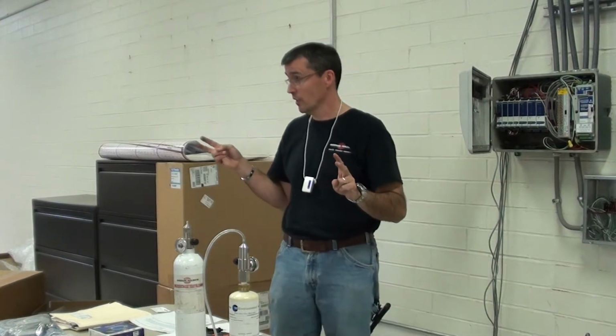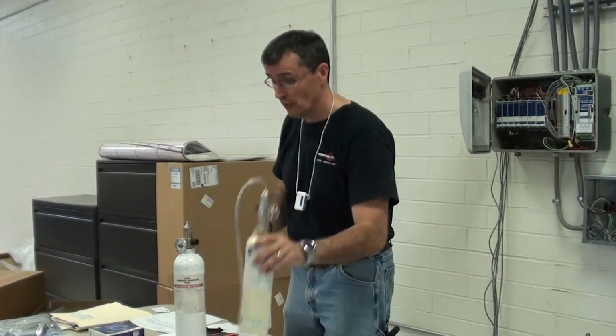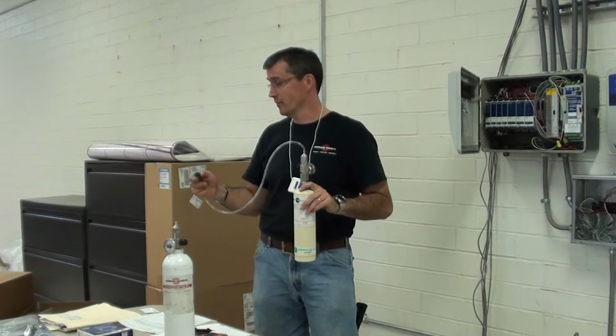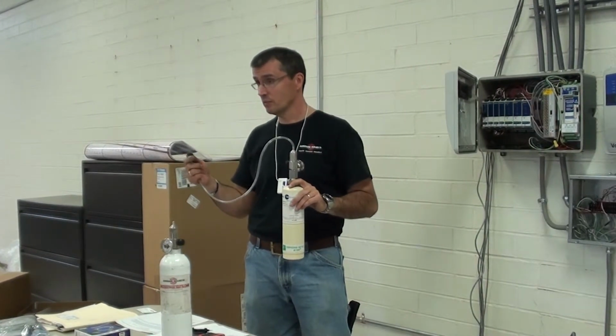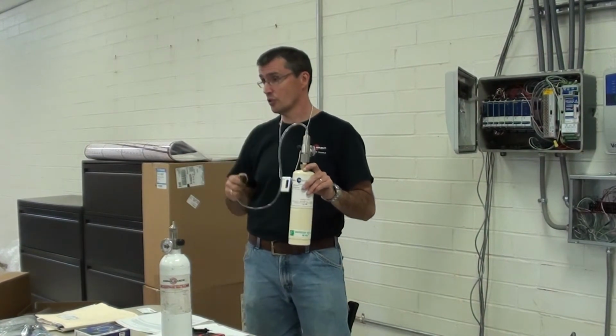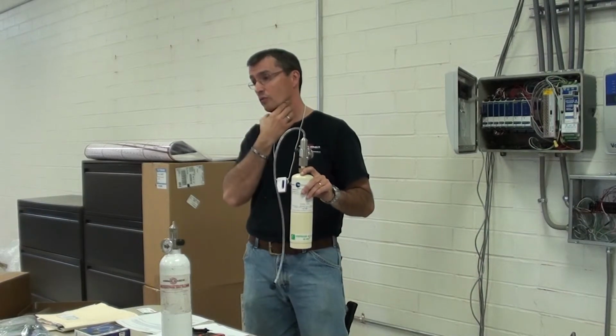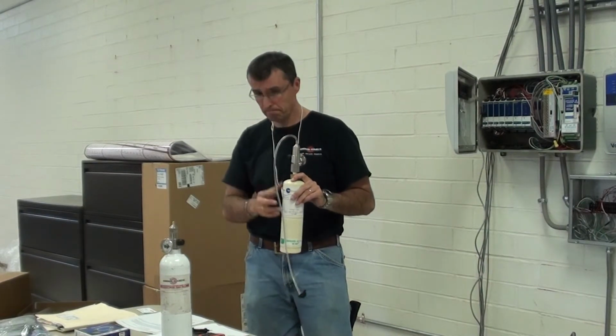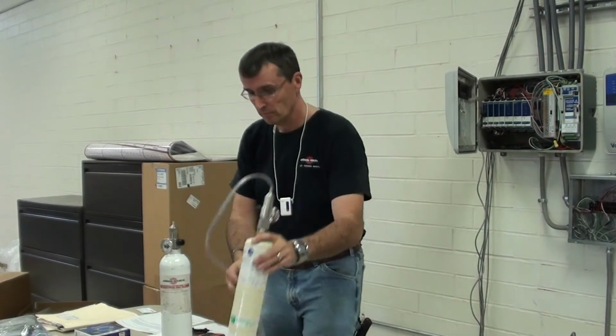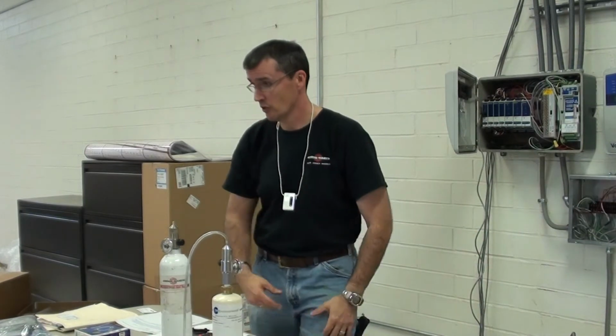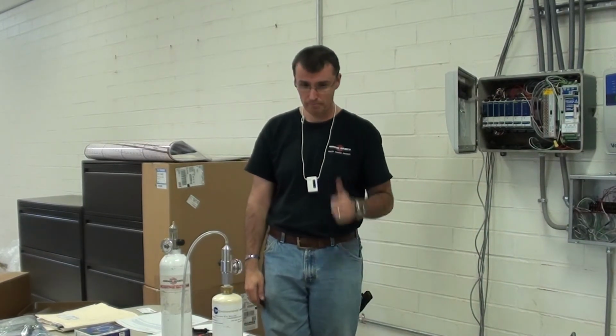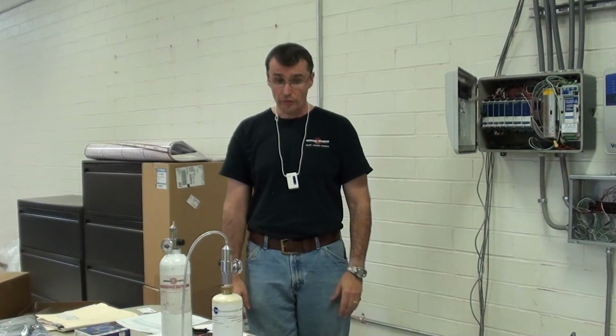Now, if you were just going to do a bump gas response check, you would go to each one, take your span gas, apply it for, say, 15, 20 seconds, make sure that you have a gas response for each cell, and verify it in the Vortex. Mm-hmm. All right. Good? Any questions on calibration? Nope. All right, so we kind of went over everything.